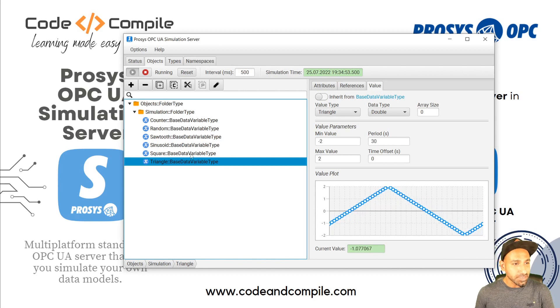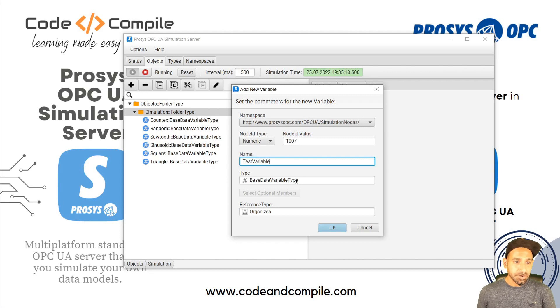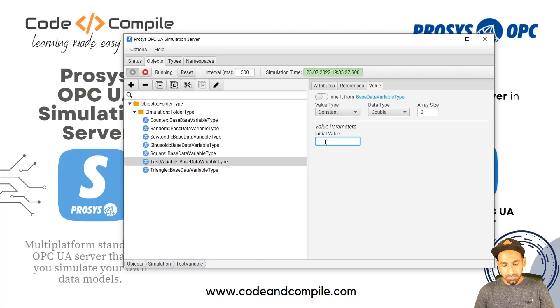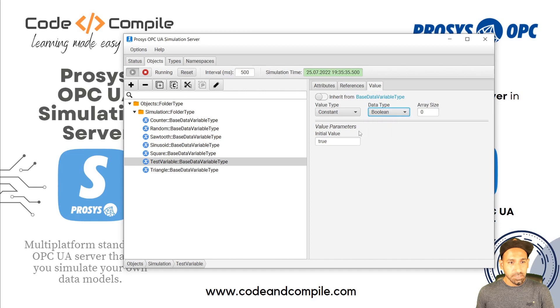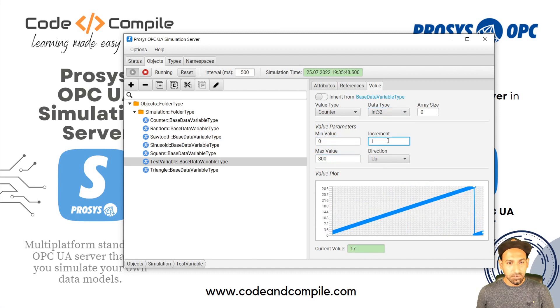Interestingly, you can also add your own variables. Just right-click and select Add Variable. Let's name it 'test variable'. It has a predefined node ID, its namespace comes from OPC UA simulation nodes, node type is Numeric, and its type is Base Data Variable Type by default. Click OK and you have your test variable. You can inherit its values from Base Data Variable Type, or define the value yourself. For example, set it as Constant with value 45. You can set it as Boolean with true or false, or configure it as a counter with Int32, minimum 0, maximum 300, increment 1, direction up.